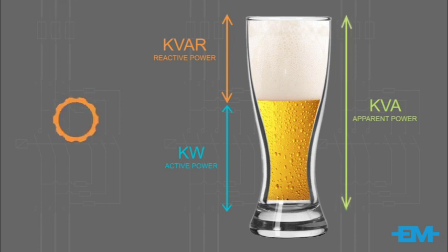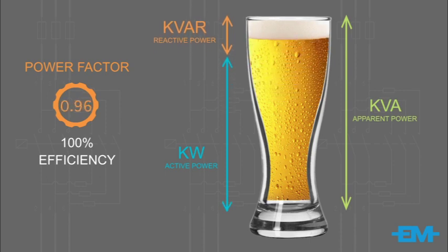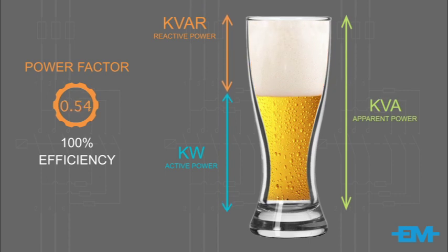The total contents of the glass — the beer and the foam — is represented by KVA, and you pay for both. A power factor of 1 would mean 100% of the supply is being used efficiently, therefore there is no reactive power; KVAR would be very small and the foam would be approaching zero. Unfortunately, a power factor of 1 is not obtainable because equipment such as electric motors, welding sets and fluorescent lighting create an inductive load which will cause the power factor to become less than 1.